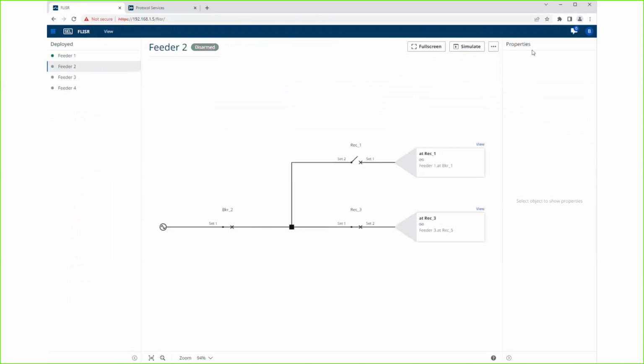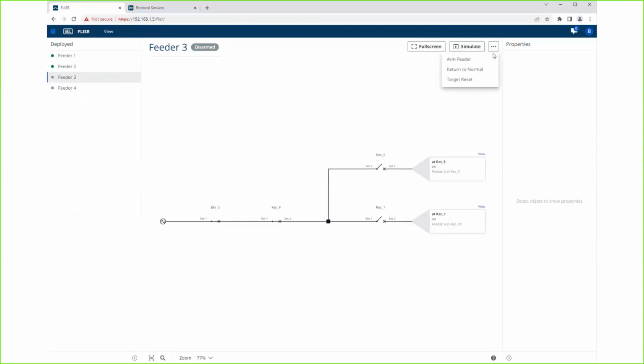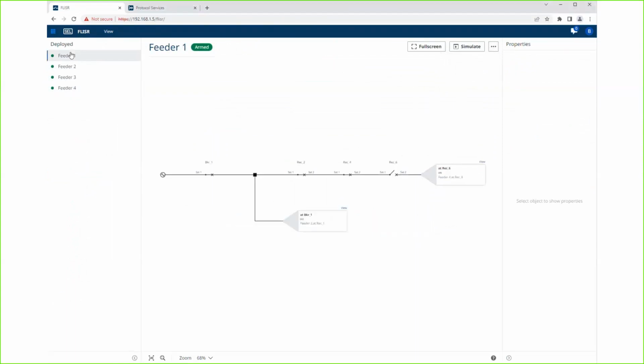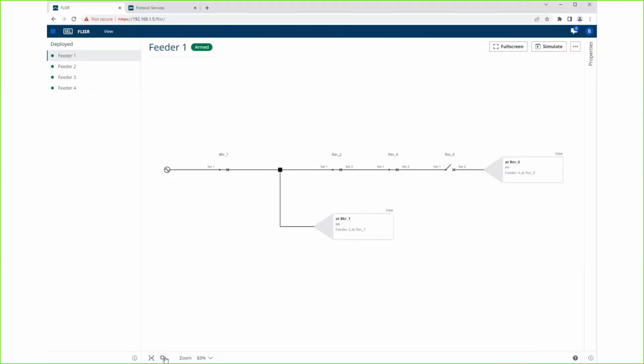So now I can start arming these circuits, and we're following the same paradigm here. You have a little dot next to each feeder in the list over there, and that dot will turn green if it's armed. You'll see a little lightning bolt if there's a fault. If there's an issue with it, you'll see that warning symbol that you saw briefly a second ago. So now I can create a permanent fault. I'm using an RTAC to generate all this DNP data, but this FLISR system is armed.